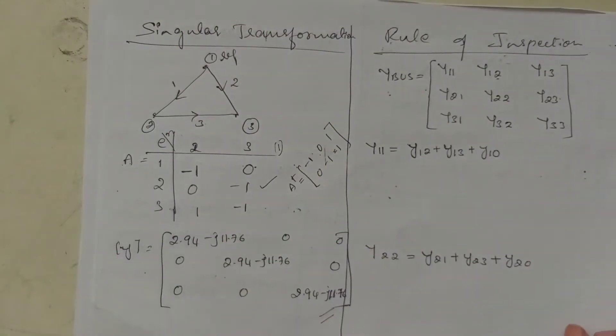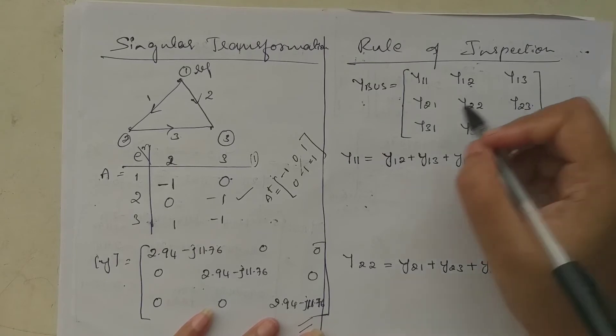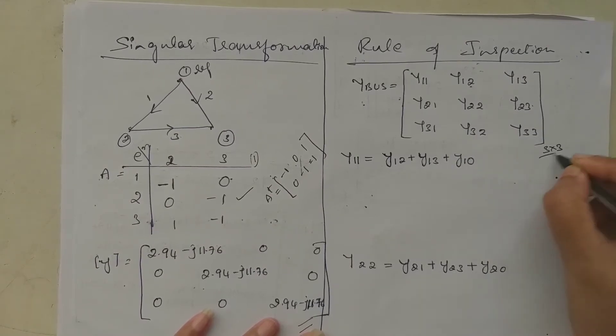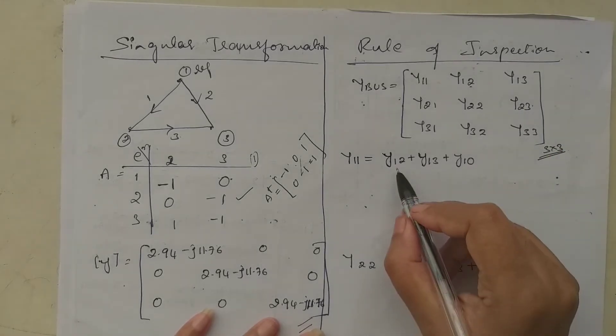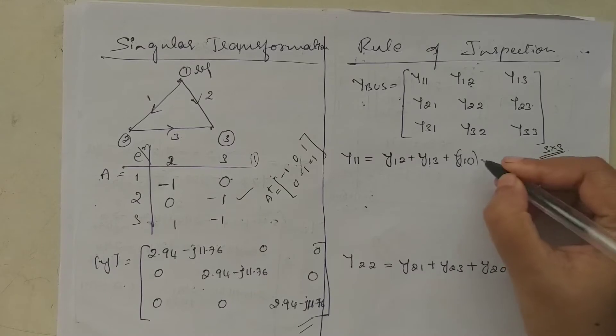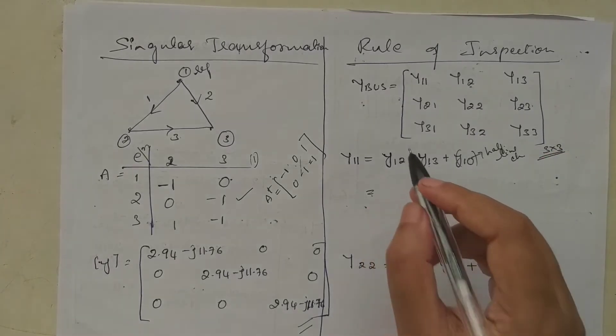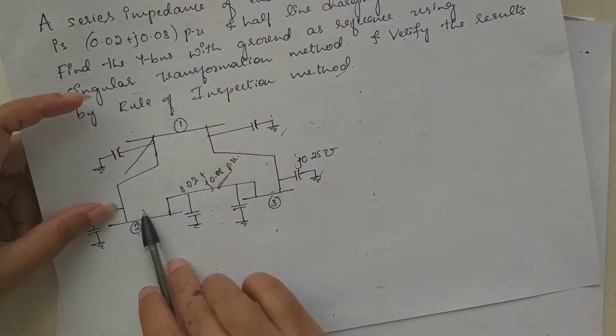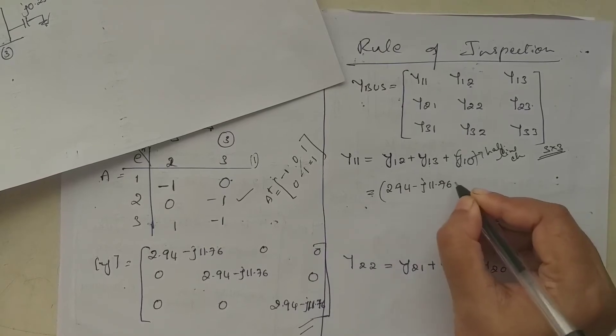Now for the rule of inspection method: Y_bus is formed as a 3×3 matrix with elements Y11, Y12, Y13, Y21, Y22, Y23, Y31, Y32, Y33. For this problem, Y11 equals Y12 + Y13 + Y10, where Y10 is the half-line charging admittance. Y12, which is the reciprocal of Z12, equals 2.94 - j11.76, and again Y13 = 2.94 - j11.76.